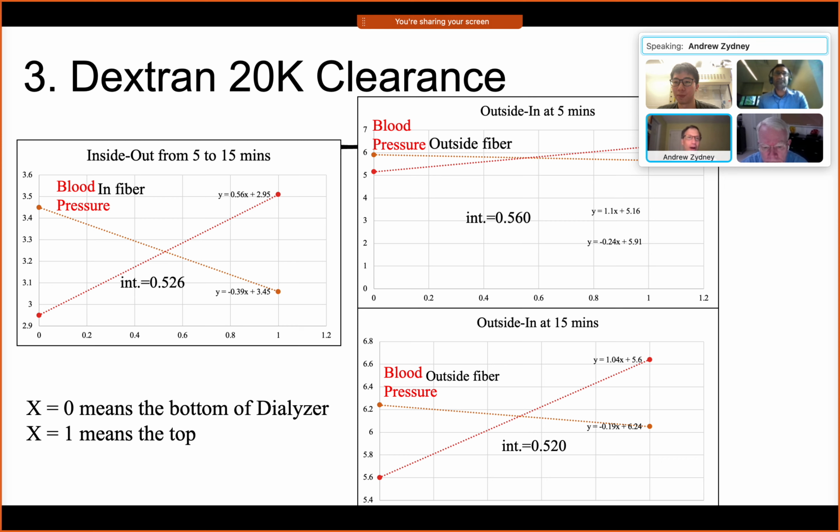They're not very large across the headers coming in and out, and they're not the same geometry on the dialysate side as on the blood side. So those can cause small discrepancies. I don't think it's worth worrying about any of that. The differences are not dramatic. But my guess is if you could actually measure the pressure in the device, they're probably crossing even closer to the midpoint than what you're measuring.